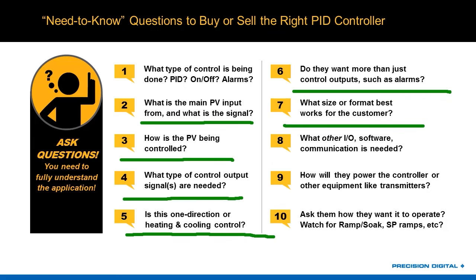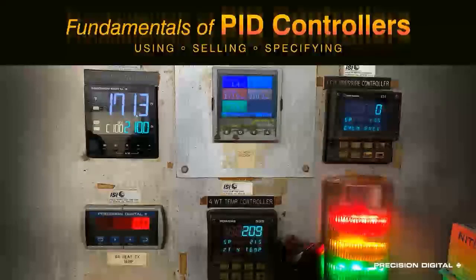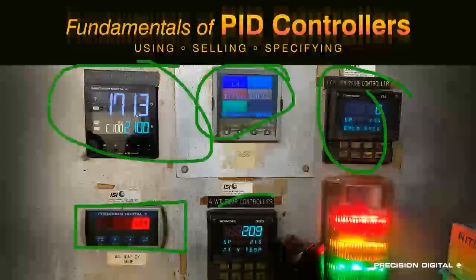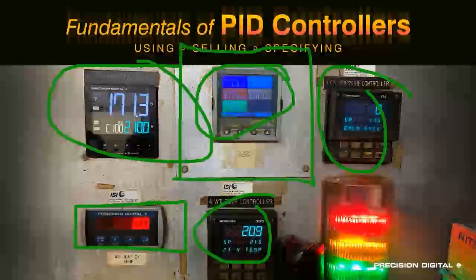If I go back to the original photo from this presentation here, you can see, okay, great, I've got a 1/8 DIN cutout down here for a Trident panel meter, and then these are all 1/4 DIN cutouts. This plate that you see around this center one is probably because it was the wrong size. They probably had a larger unit in there, and then they had to make an adapter plate. How are you going to seal that? It becomes a hassle. So know the size of the unit that you want for the panel that you have.